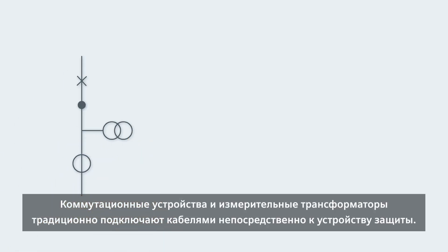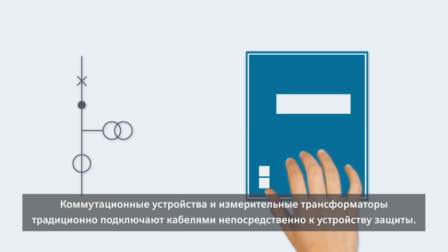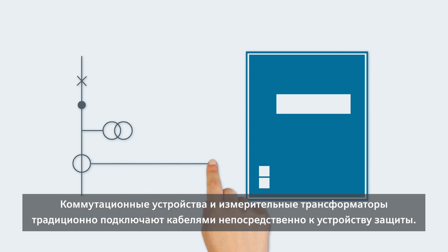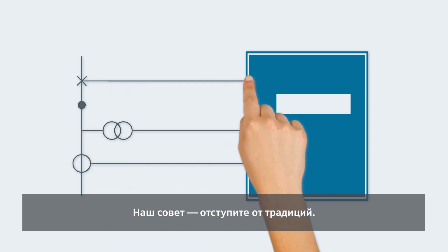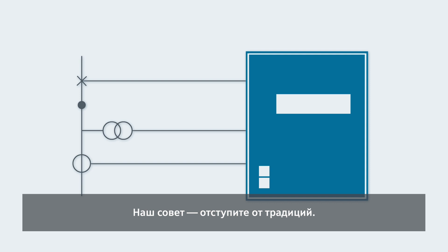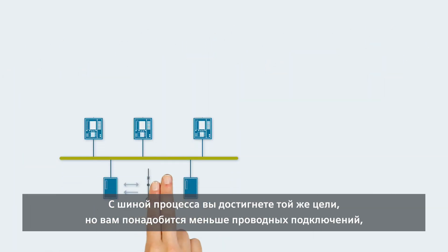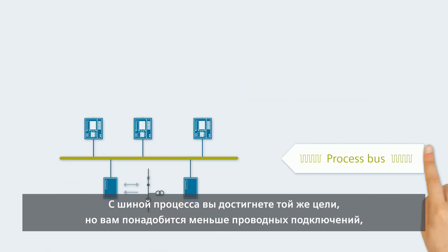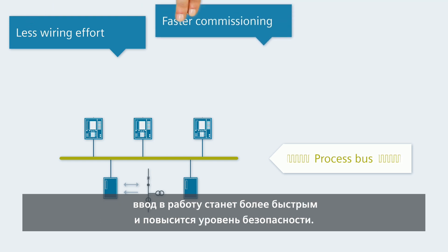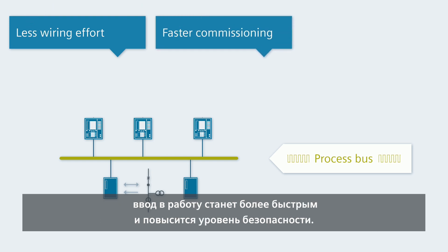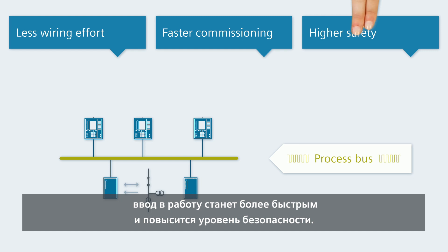Switching devices and instrument transformers are traditionally wired directly to the protection device. Our tip? Break with tradition. With a process bus you achieve the same goal, and that with less wiring effort, faster commissioning, and higher safety.